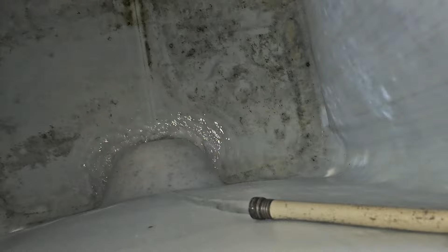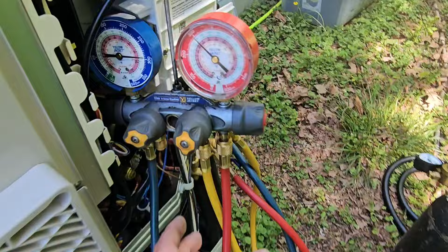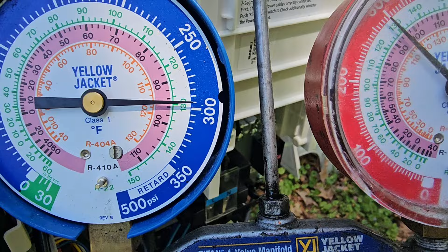Almost filled up all the way. Now that I've got the water level where I want it, I'm going to wait and watch for bubbles. And I'll show you the nitrogen pressure test, or pressure that I've got on it. Still got 300, well, right below 300, that mark right there, it's 295. Now to move forward and pull a vacuum, I'm going to let the nitrogen out.